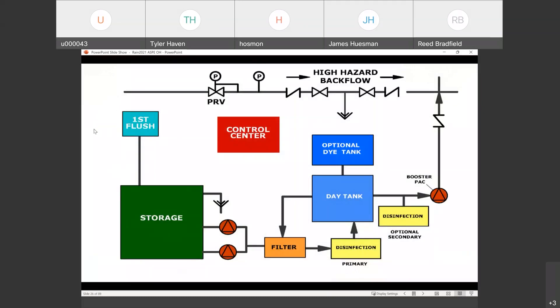First is the first flush — the first 10 to 15 minutes of that rain event, you get 95% of the pollutants off of that surface. First flush is probably one of the most important parts of these systems. Understanding where we're pulling water from — is it a small roof, a big roof, a paved area, a parking deck? That first flush filter is the first line of defense to my storage. Storage is probably the most expensive part of these systems, but if we have to do stormwater management anyway and there's a regulation requiring some sort of means of storage — whether above ground or below ground, concrete, steel tank, fiberglass, or plastic — it doesn't make any difference.